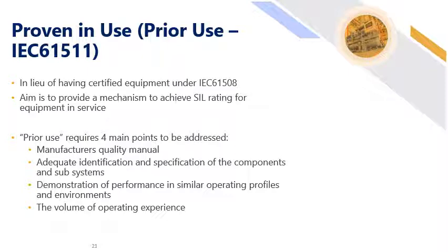But the main thing is you've got to make sure that the manufacturer's quality manual is in place. There has been adequate identification and specification of components and subsystems. There is a continued demonstration of performance in similar operating profiles and environments. So this is where you can get generic data from to back up your use of a particular device.